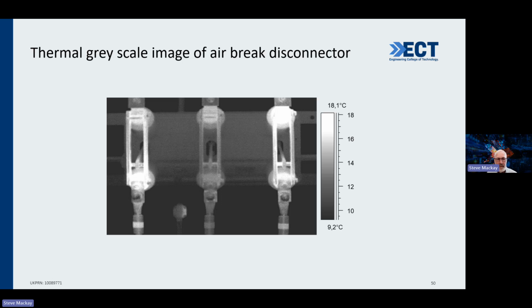What does temperature mean when you're looking at these disconnectors? What does the temperature mean? Is high temperature a good thing or a bad thing? Just put there, yeah, low current. Yeah, so the middle has lower temperature, low current. Thank you very much, Mark. Absolutely right. So the higher heat means you've got a potential problem here. So normally you'd see probably one of them out of kilter, but here we've got two which are higher temperatures. So there's something happening here which we need to investigate further. Obviously, very useful to look at the temperature levels.